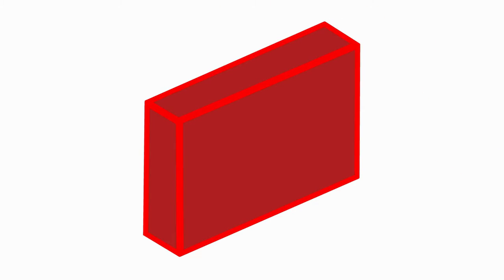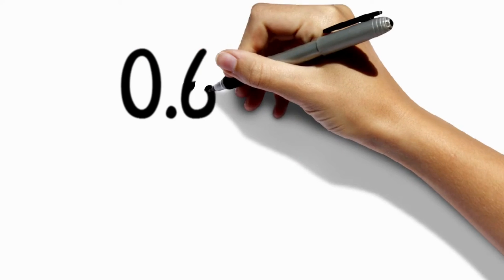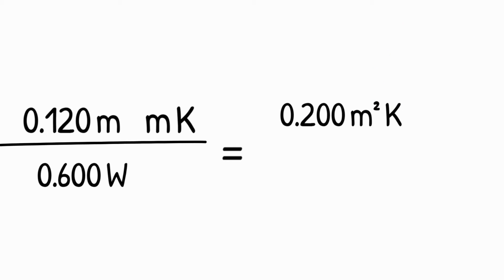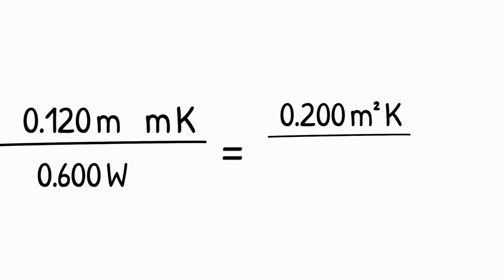Okay, let's assume we have a 12 centimeters thick outer layer, and 12 centimeters are 0.12 meters. We put this over the thermal conductivity of this material, which is 0.6 watt per meter kelvin. That gives us the resistance of this layer of 0.2 square meters kelvin over watt.